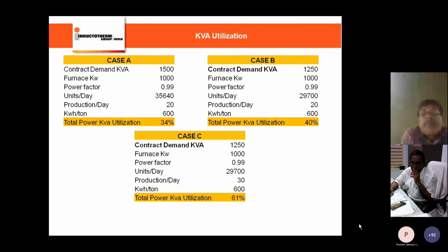So case C: let's talk about a 1250 kVA contract demand. Still the furnace kilowatt is 1000, power factor is unity, and the units allotted per day are 29,700. But the catch here is the production from the furnace is 30 tons. When you increase the production to 30 tons, the utilization goes to 61%. How does this happen? Only because of how effectively the furnace is utilized with dual tracks, multi tracks, or tri tracks. So you will need to calculate producing more kgs per given kVA, thereby reducing losses and paying the minimum demand charges.